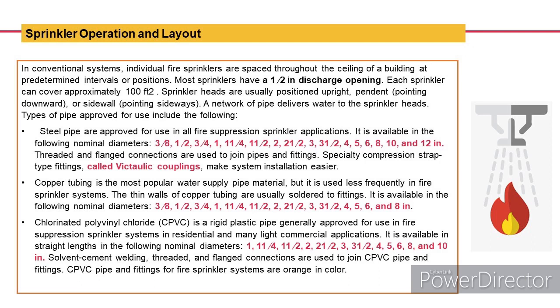6, and 8 inches. Chlorinated polyvinyl chloride, or CPVC, is a rigid plastic pipe generally approved for use in fire suppression sprinkler systems in residential and many light commercial applications. It is available in straight lengths in the following nominal diameters: 1, 1 1/4, 1 1/2, 2, 2 1/2, 3, 3 1/2, 4, 5, 6, 8, and 10 inches. Solvent cement welding, threaded, and flanged connections are used to join CPVC pipe and fittings. CPVC pipe and fittings for fire sprinkler systems are orange in color.